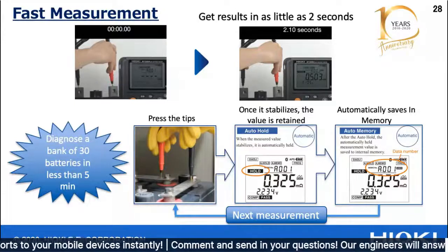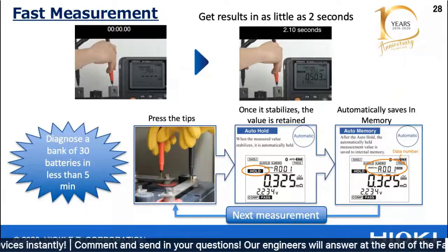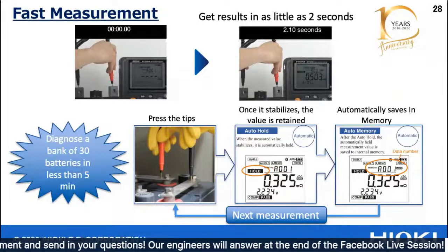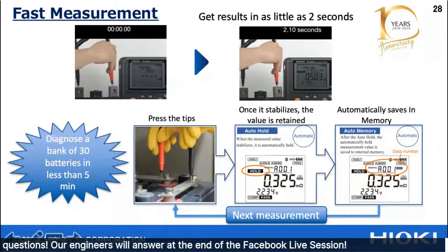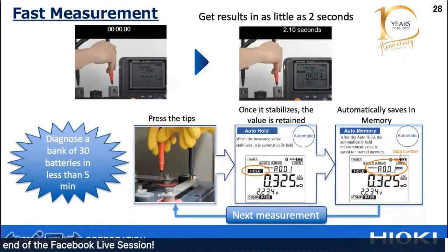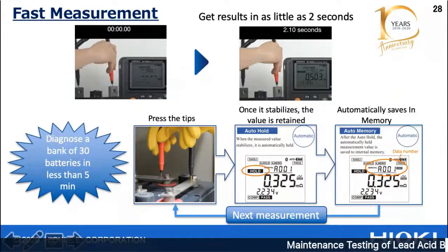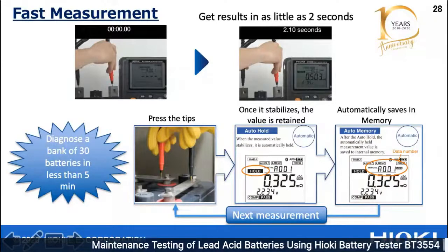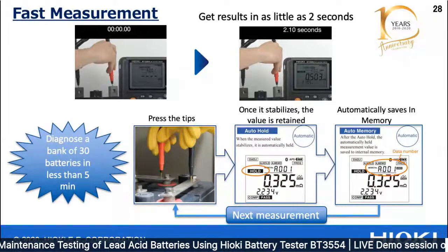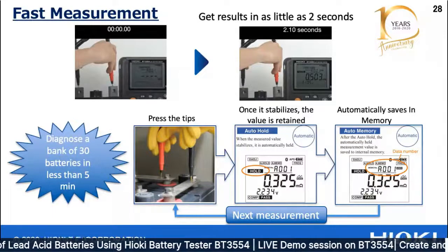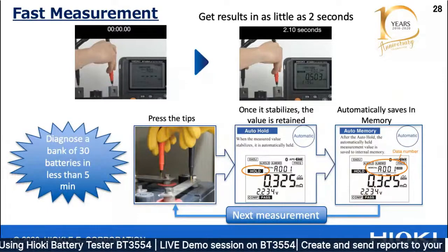The process to perform the measurement is to press the tips onto the electrode like this. Once the measurement stabilizes, the value is retained and automatically saved in memory. Then you can repeat for the next battery. So imagine if you have 30 batteries - every measurement can be taken within 2 seconds. That's quite fast and very productive for your battery maintenance routine.